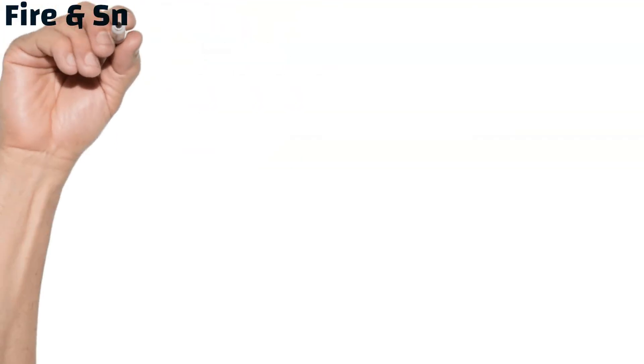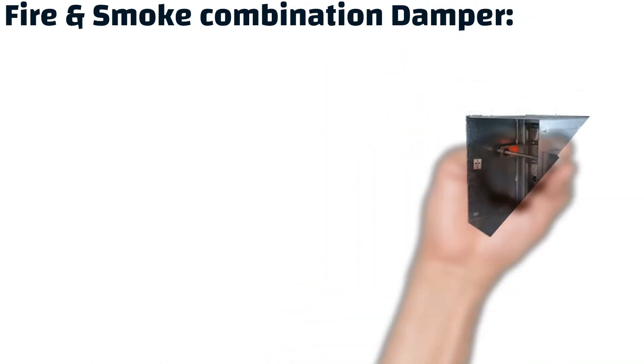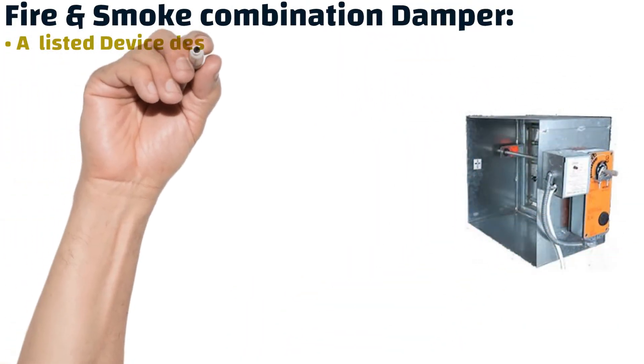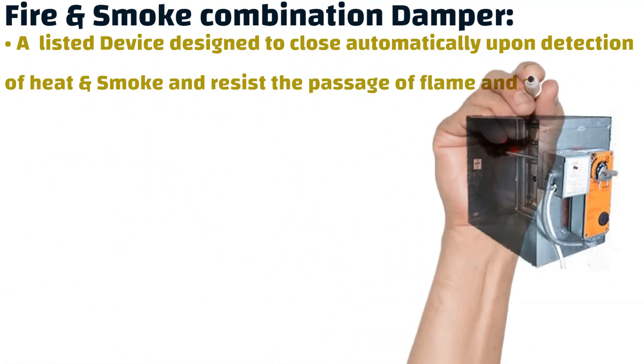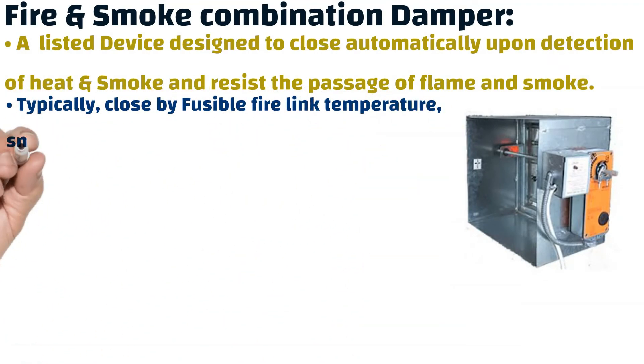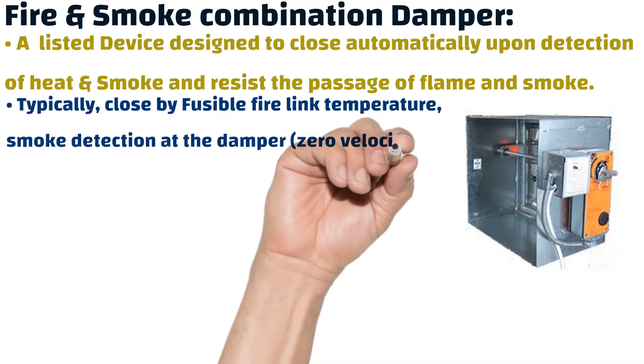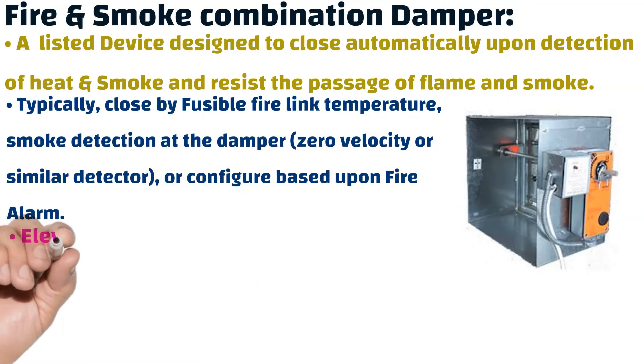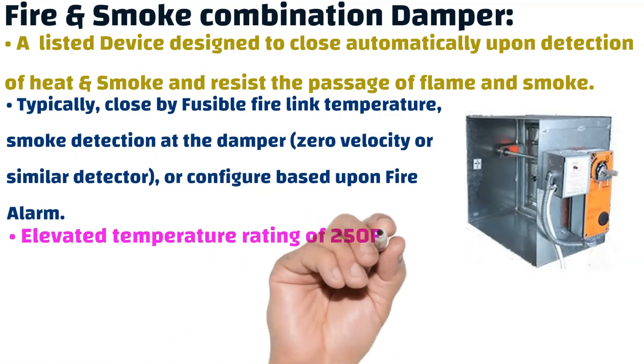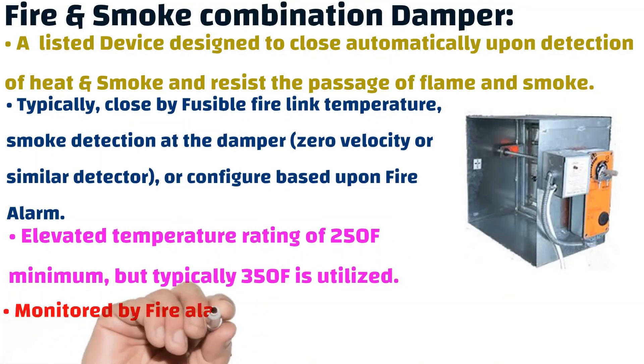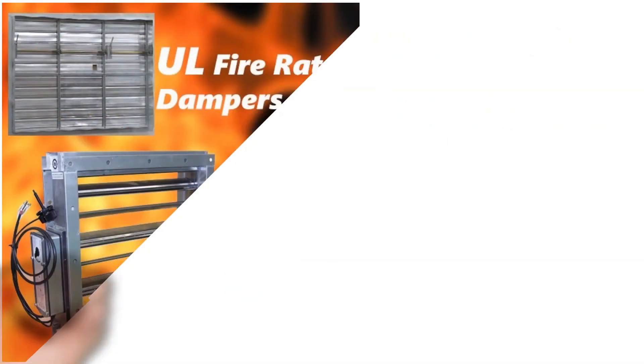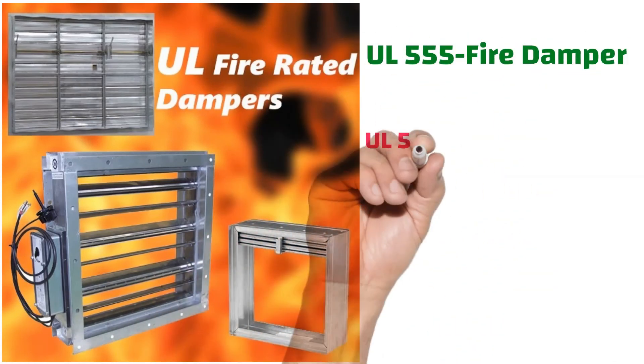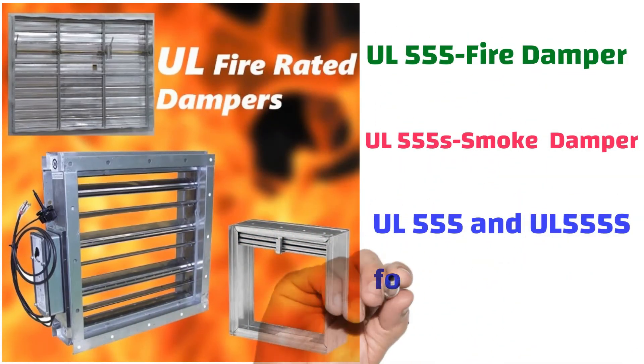What is a fire and smoke combination damper? It is a listed device designed to close automatically upon detection of heat and smoke and resist the passage of flame and smoke. It is typically closed by a fusible fire link temperature or smoke detection at the damper, configured based upon fire alarm, and monitored by fire alarm for open and closed position — closed position only for smoke control, and non-smoke control as well.